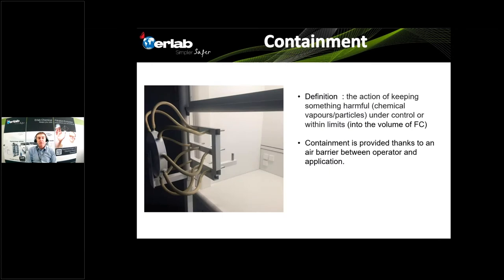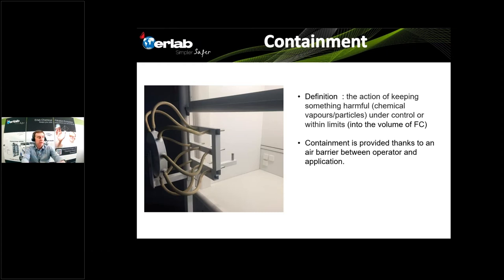When we try to define containment, I extracted a definition from the web and applied it to fume hoods. It can be defined as the action of keeping something harmful — for example, chemical vapors or particles — under control, within limits, the limits of the enclosure. If you use a chemical on your worktop, thanks to the air barrier, you create a barrier between the vapors emitted by your beakers and the user.